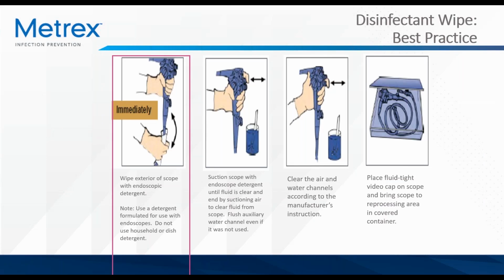The last pre-cleaning product we want to cover is disinfecting wipes. Some medical device manufacturers recommend use of a disinfecting wipe to remove gross debris prior to reprocessing. This is a type of pre-cleaning that can vary from device to device, so it's important to review IFUs for procedural instructions. What you're looking at here is an example where wiping is the recommended pre-cleaning step for the scope in the drawing. You'll see disinfecting wipes commonly recommended in the reprocessing instructions for ultrasound probes too. Ultrasound probe IFUs often recommend use of a disinfecting wipe to pre-clean prior to terminal high-level disinfection.